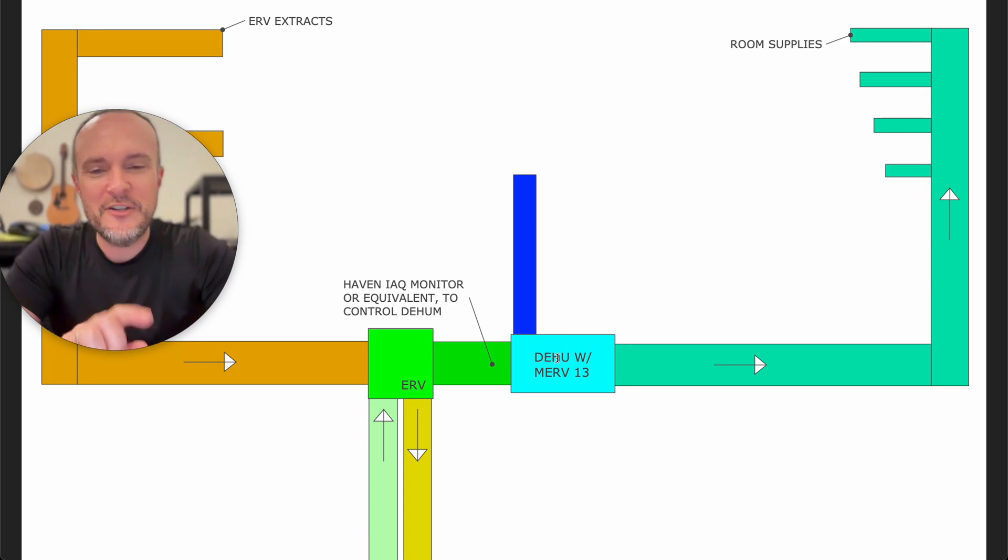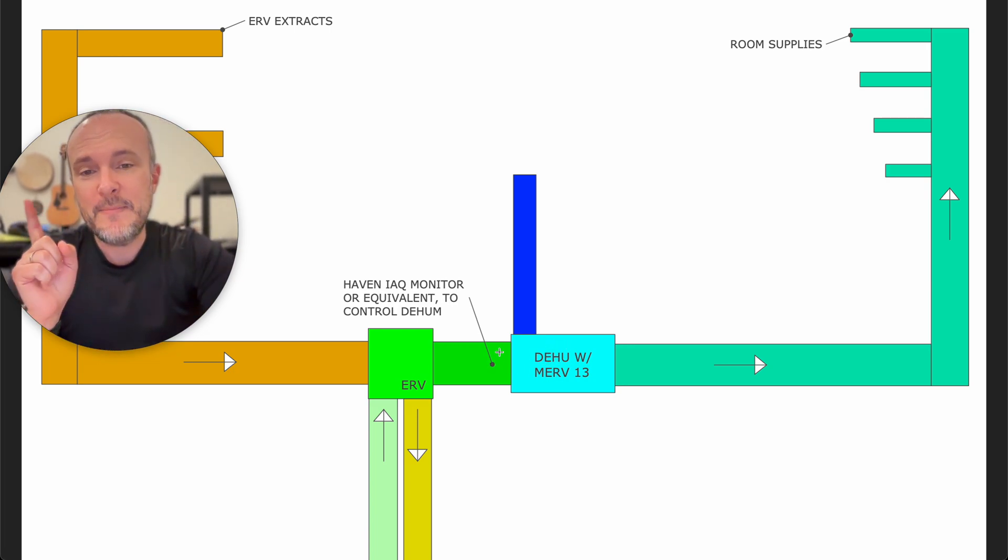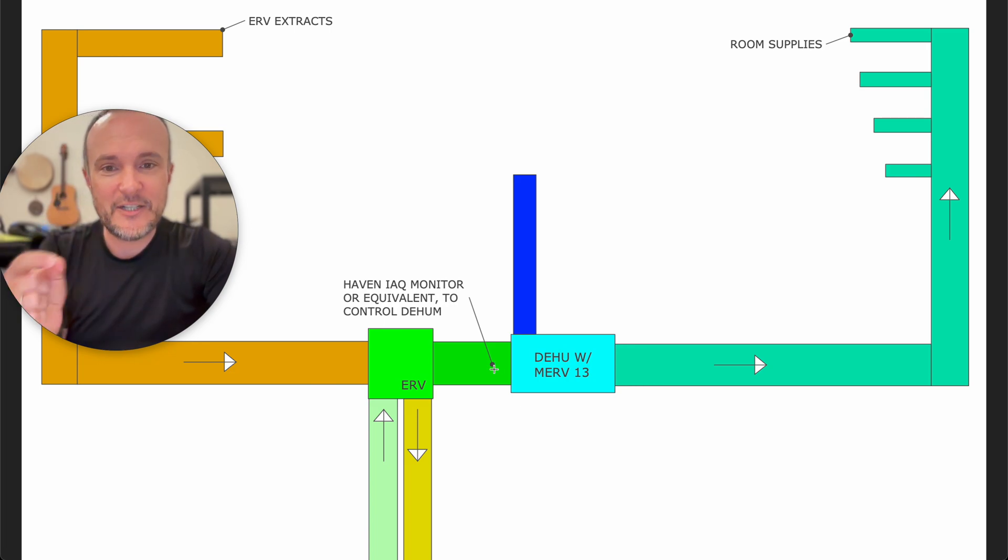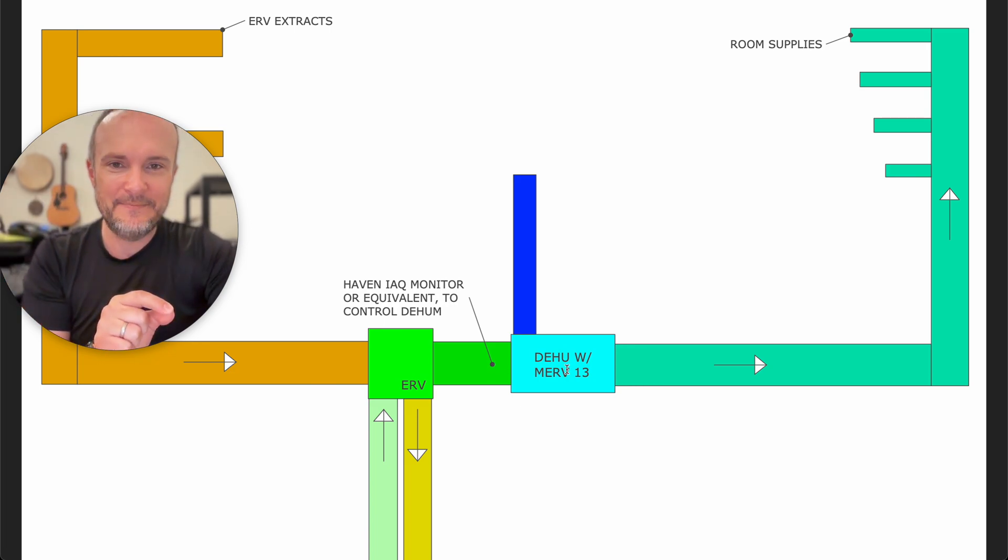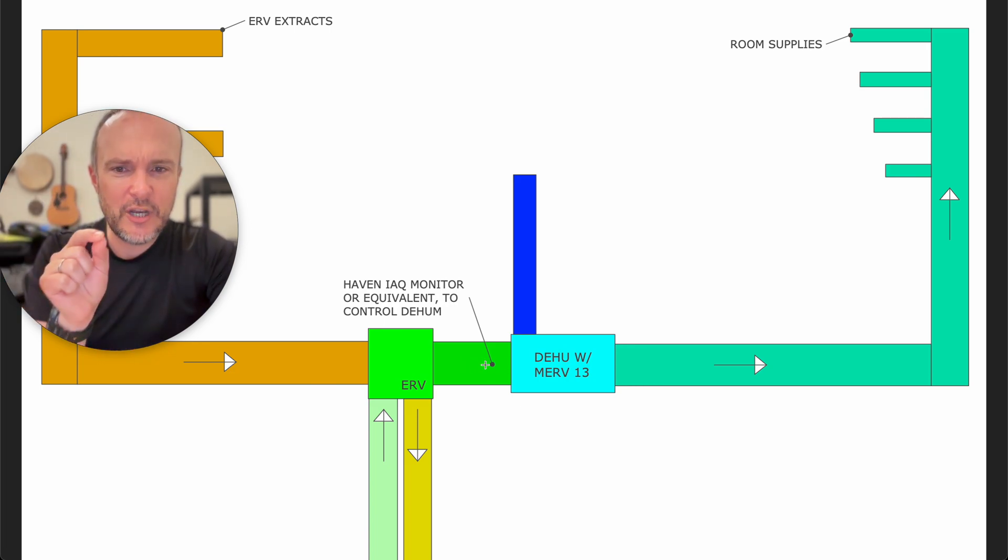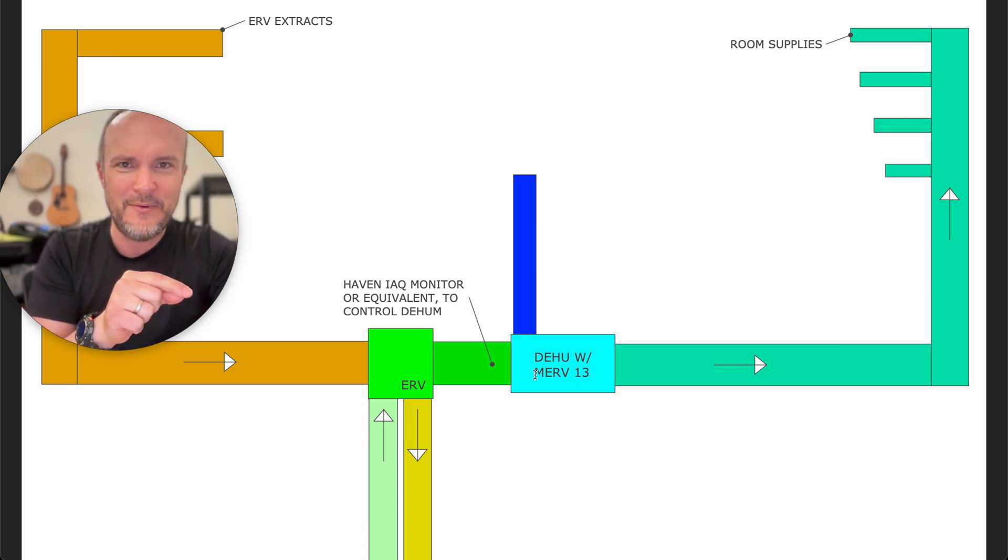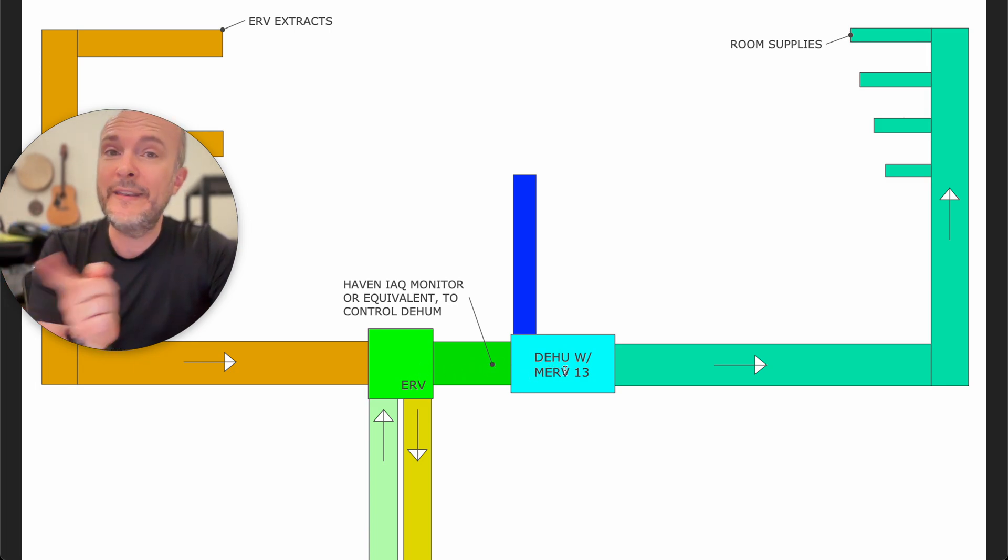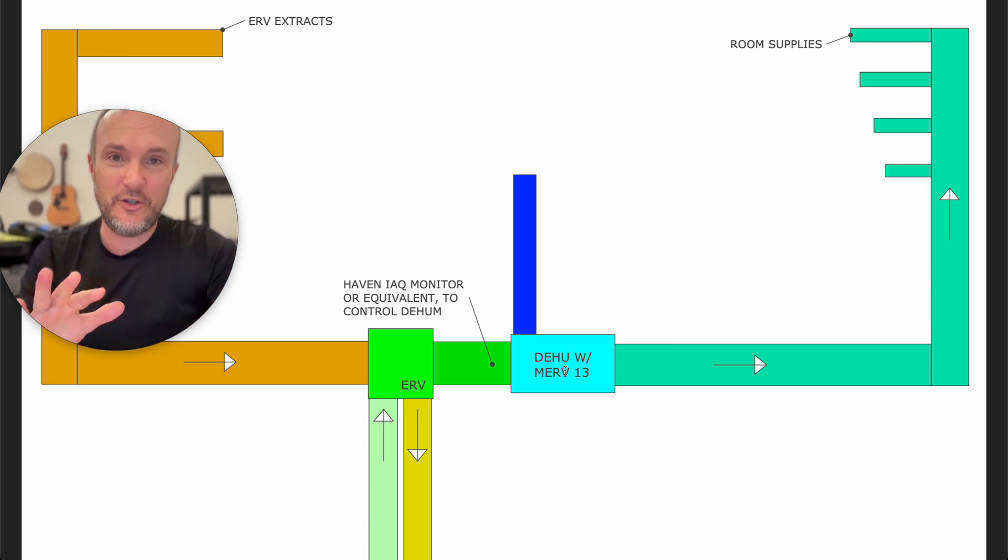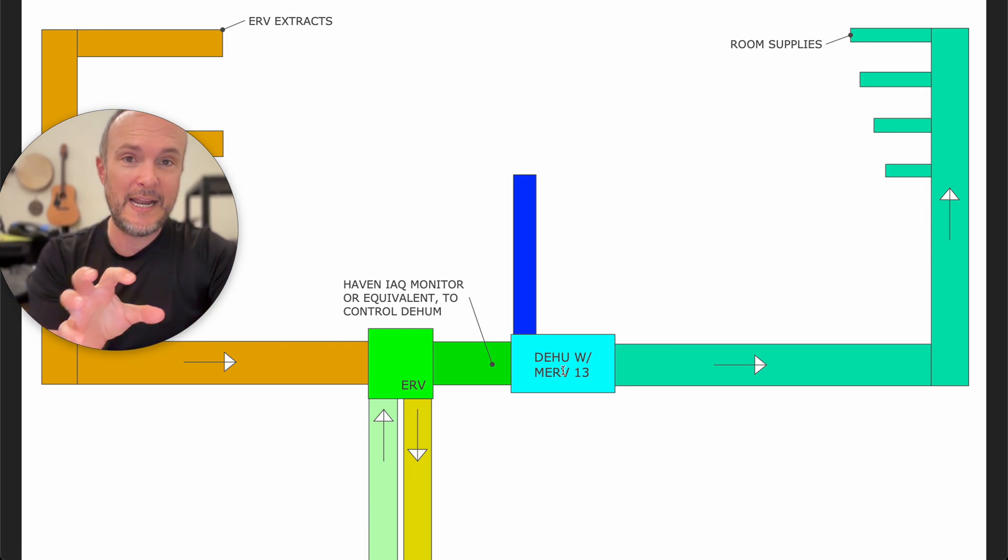So the first thing you need to do is make sure that the sensor, the humidity sensor that activates the dehumidifier, gets injected into this ductwork between the ERV and the dehumidifier. Otherwise, the dehu will not be able to know until it's way too late that it needs to turn on its compressor and start drying this air that's being fed to it.